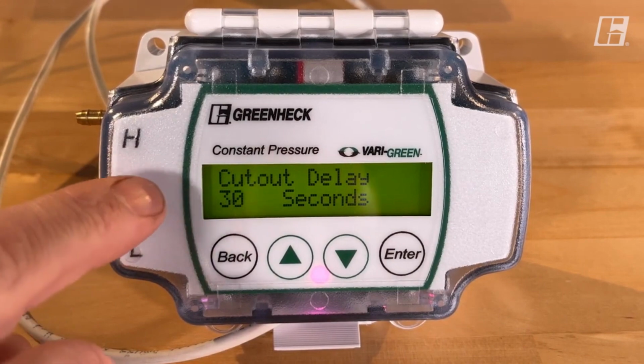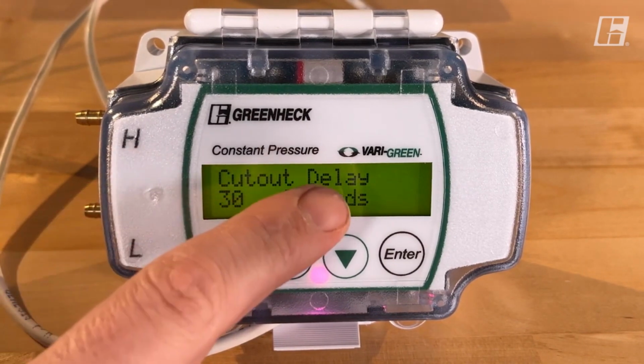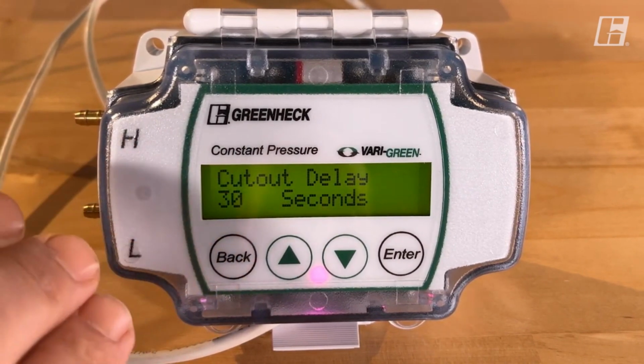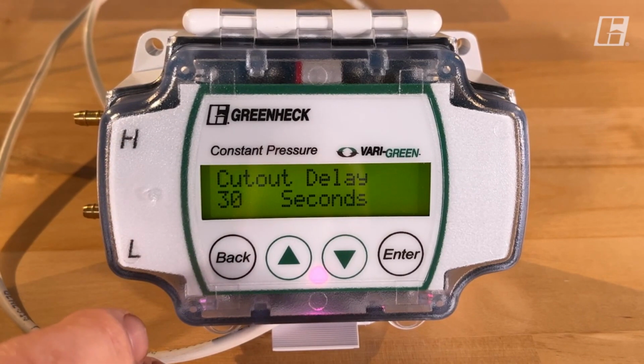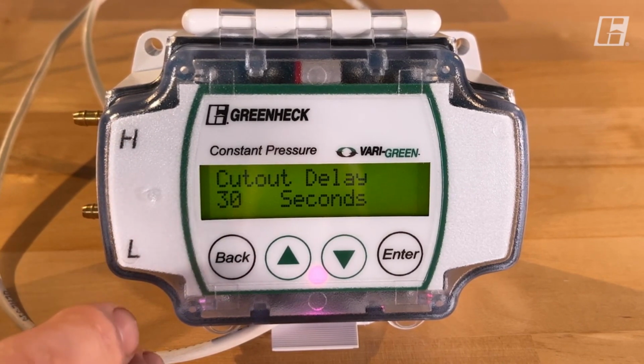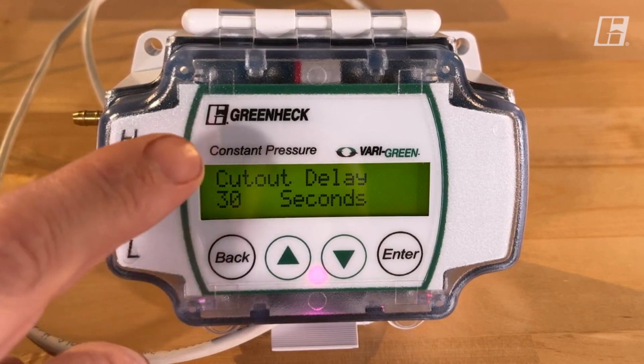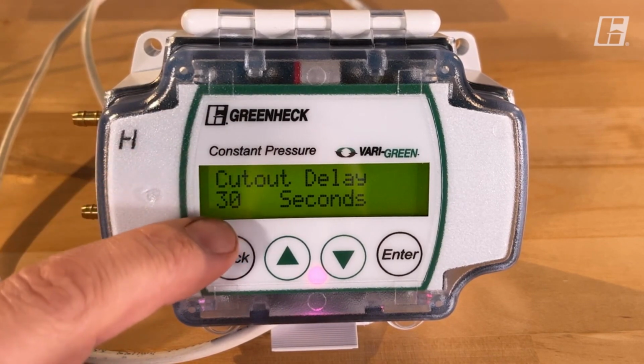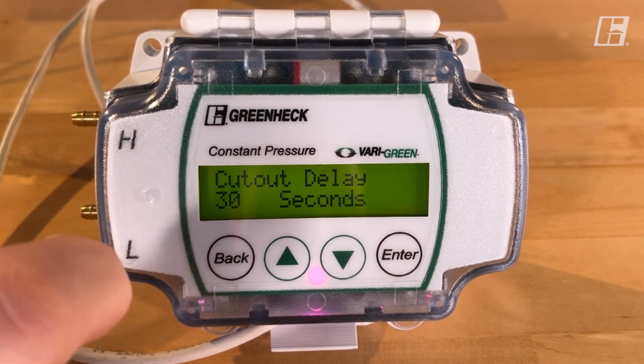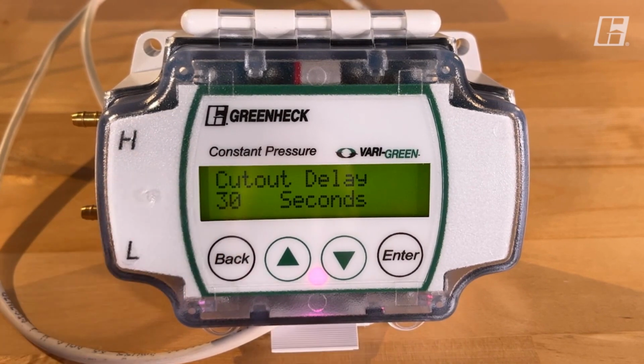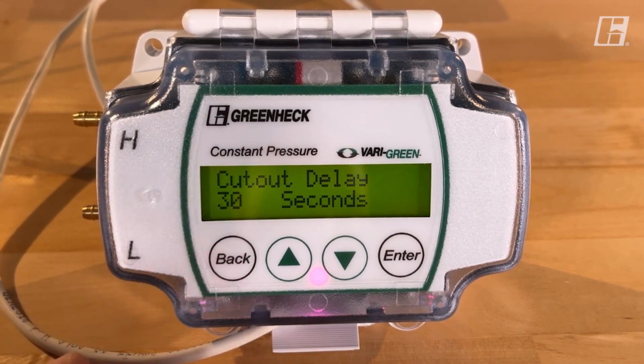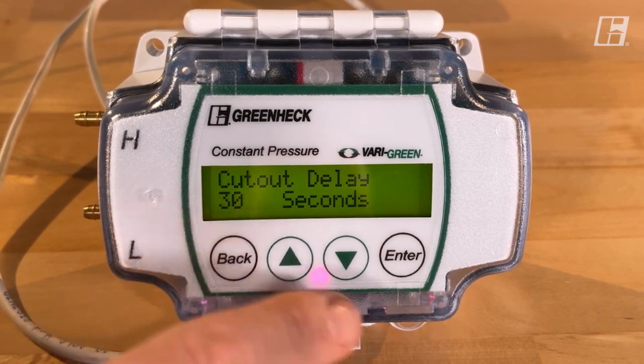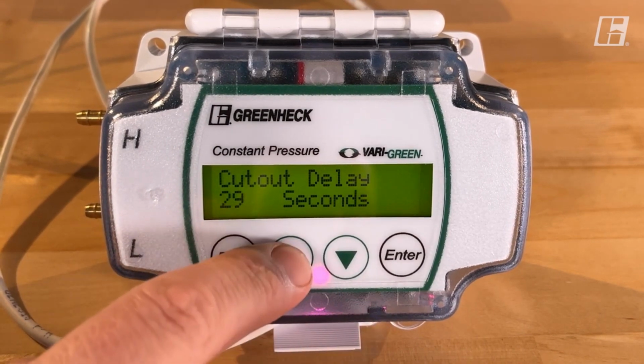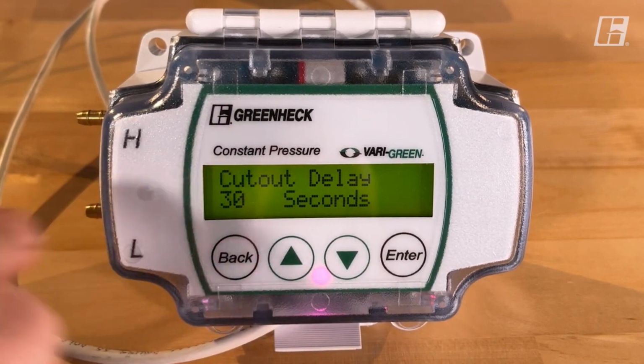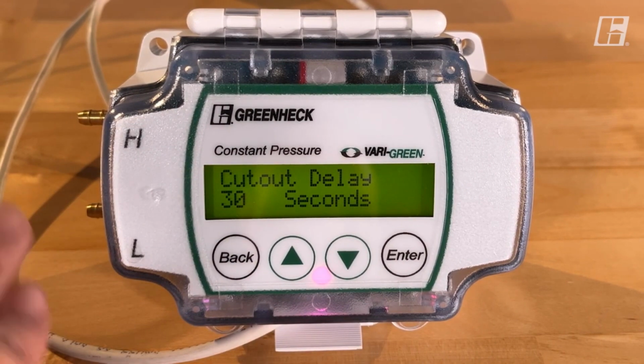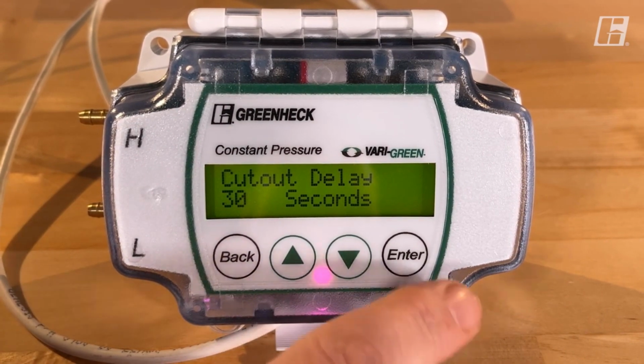Our second parameter for cutout is the delay. So if we are needing less than 20% of the fan's capability to maintain our set point, we now enter cutout. This is the delay or the purge time that is going to keep the fan running to get any warm air out of the ductwork. And you can set this by 1-second intervals. After this 30 seconds, the fan will actually stop and wait for the pressure to change.